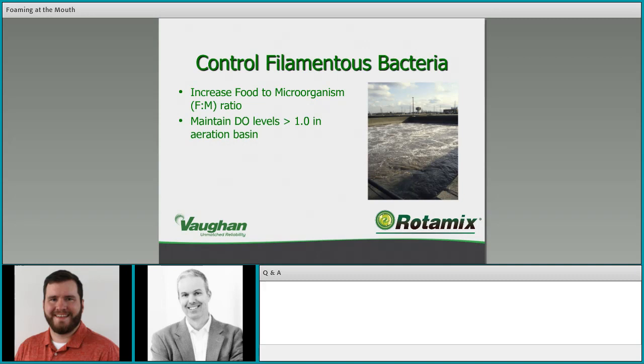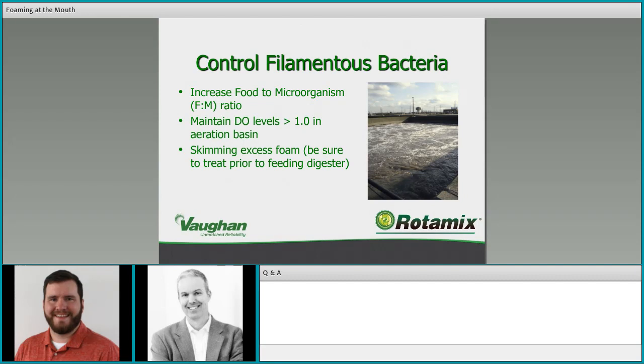Increasing dissolved oxygen will reduce filamentous bacteria levels in your activated sludge process and also help deal with foaming. Skimming excess foam is definitely a technique that works — getting those filamentous bacteria that rise to the surface out removes those bacteria. But be sure you're treating that foam prior to feeding the digester to destroy those bacteria, because if you're skimming from your aeration process and feeding it directly into your digester without deactivating, you're just loading extra filamentous bacteria into your digester.